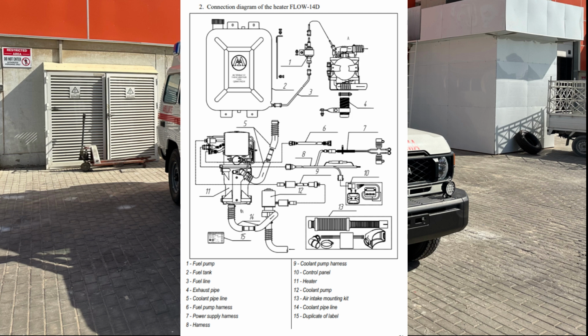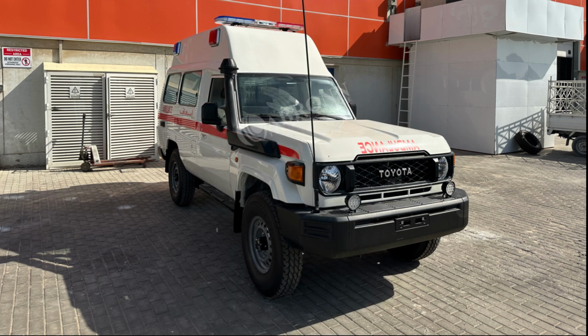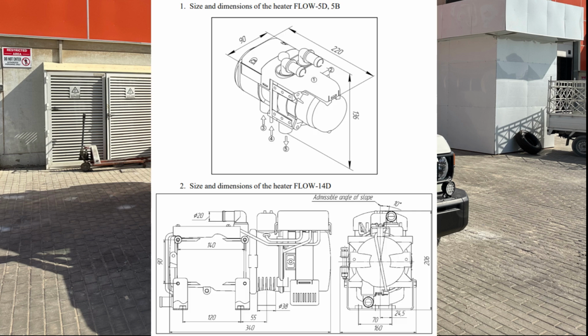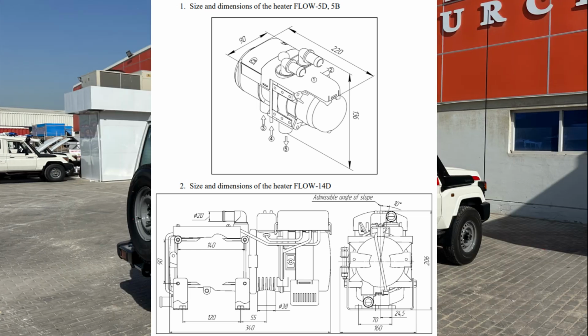Before starting to heat the coolant, the pump will start to check if the heating liquid is frozen. The heater will then power up to 100% to heat up the combustion chamber and to provide proper burning temperatures. Depending on the ambient temperature and model of the heater, this process can take up to 15 minutes. Hot liquid only flows after the heat exchanger is heated up. This process takes up to 3 to 5 minutes depending on the ambient temperature and the heater model. It does not happen instantly.